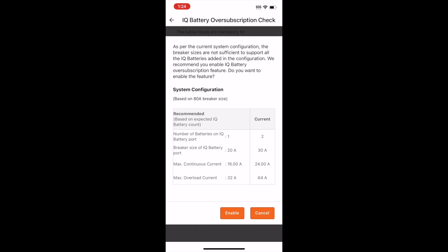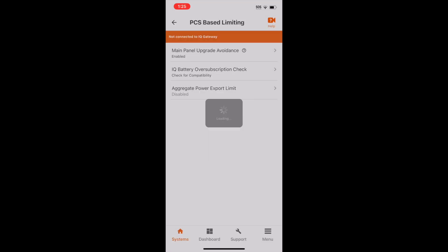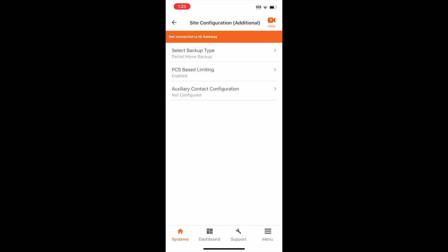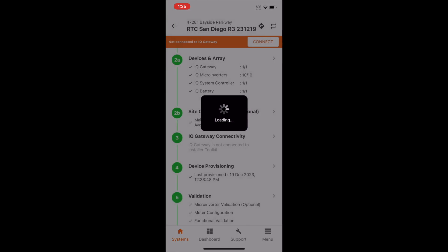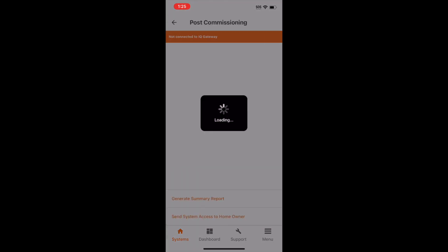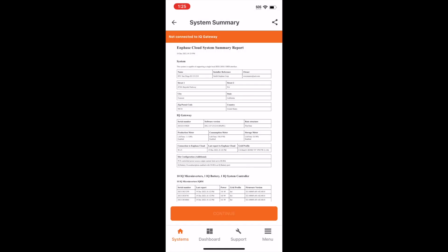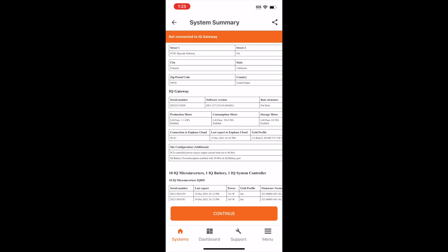You can see that the app, and therefore the system, will limit the total battery current to 24 amps, as this is the maximum continuous current allowed for a 30 amp breaker. Remember, the PCS limit is not in effect until the system is fully commissioned. To review that the settings are correct, you can view the Summary Report.